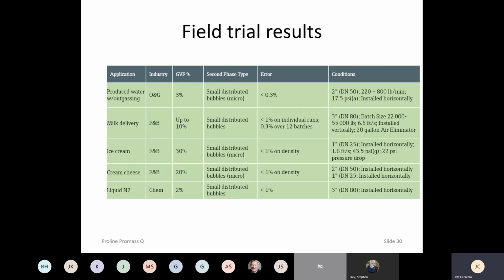These are actual cases. Milk delivery has entrained air of actually up to 10% because of the pumps and the connections, etc. We can achieve less than 1% accuracy on individual runs, 0.3% over 12 batches. Ice cream, they actually inject air or gas to lighten it up, to fluff it up. Very difficult to measure. So that's up to 30%. So we're better than 1% accuracy on density for ice cream. Same with cream cheese and even liquefied gases, liquefied nitrogen. So an extremely good result with the Q meter on entrained gas applications.